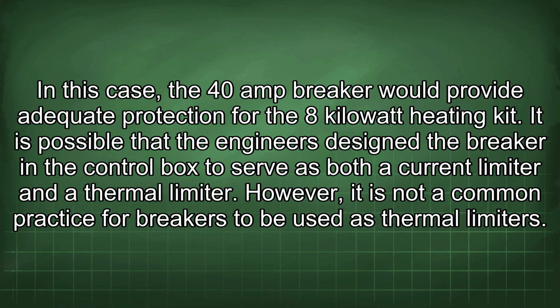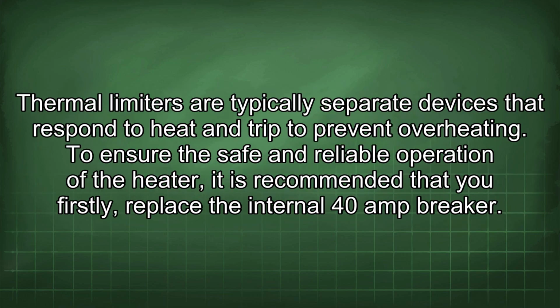kit. It is possible that the engineers designed the breaker in the control box to serve as both a current limiter and a thermal limiter. However, it is not a common practice for breakers to be used as thermal limiters. Thermal limiters are typically separate devices that respond to heat and trip to prevent overheating.